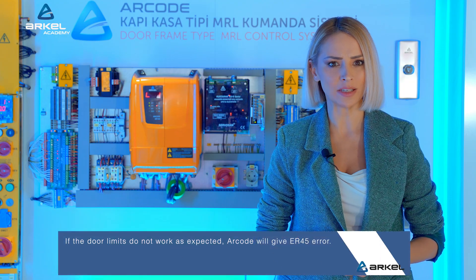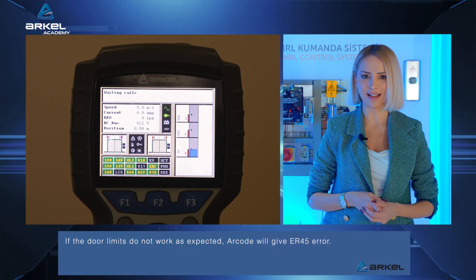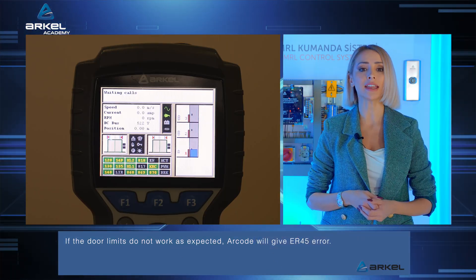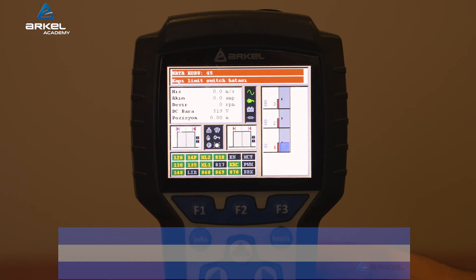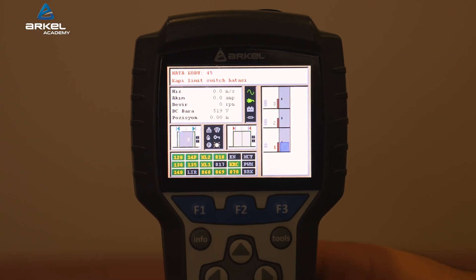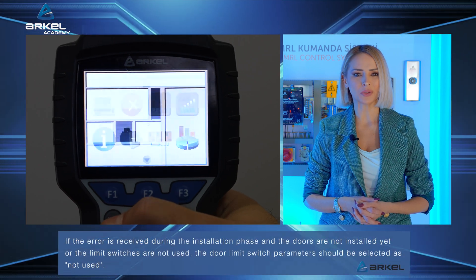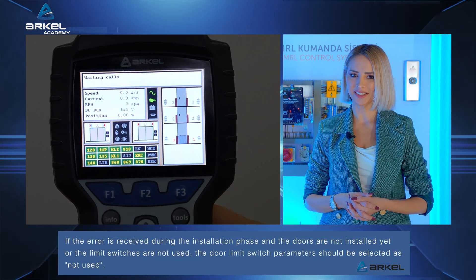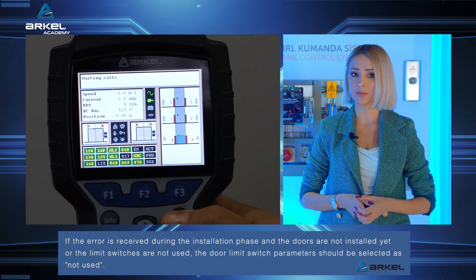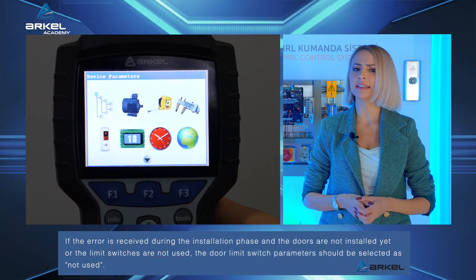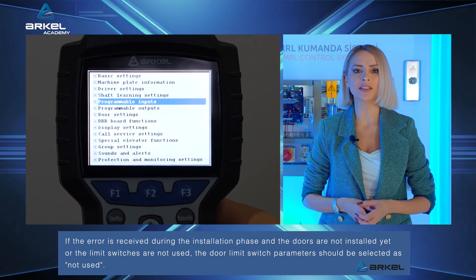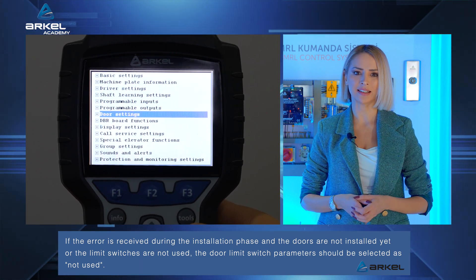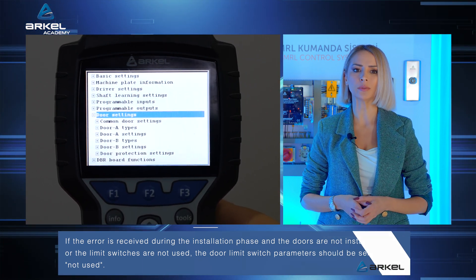If the door limits do not work as expected, Arkel will give error ER45. If the error is received during the installation phase and the doors are not installed yet or the limit switches are not used, the door limit switch parameters should be selected as not used.